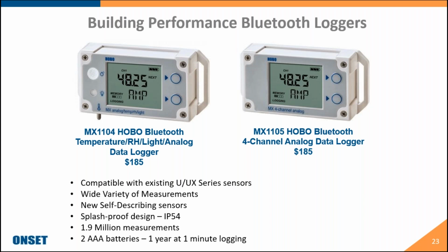It has an improved casing, which has a splash-proof design with an IP54 rating. These data loggers can store up to 1.9 million measurements before the memory fills up. And lastly, they run on two AAA batteries, which at 1 minute or greater logging intervals, you should get about a year's life out of before you need to replace them.